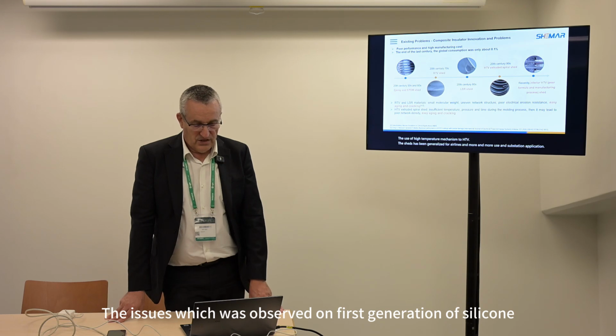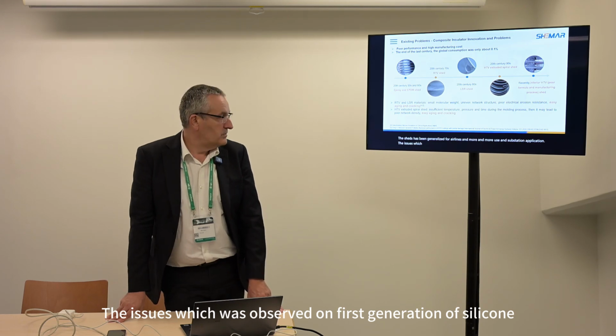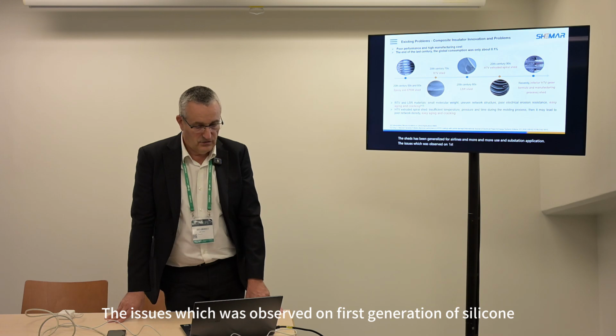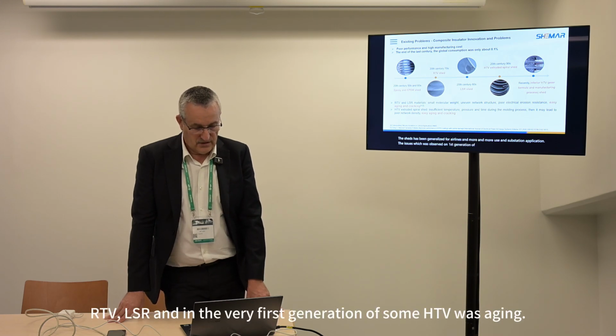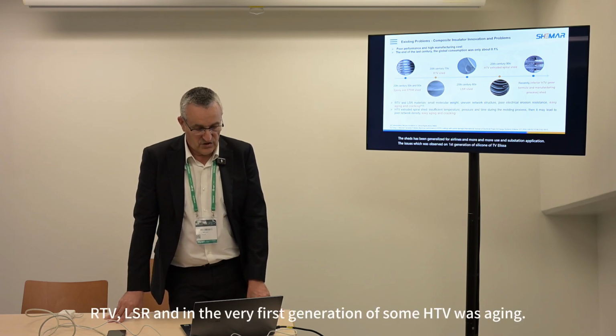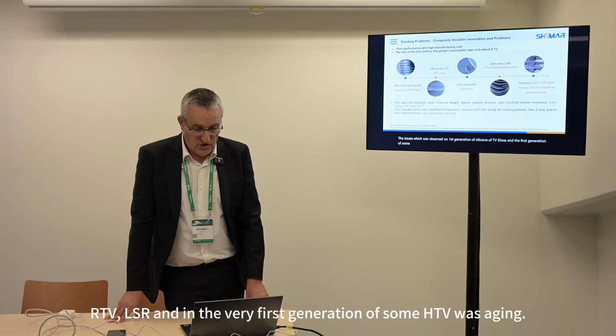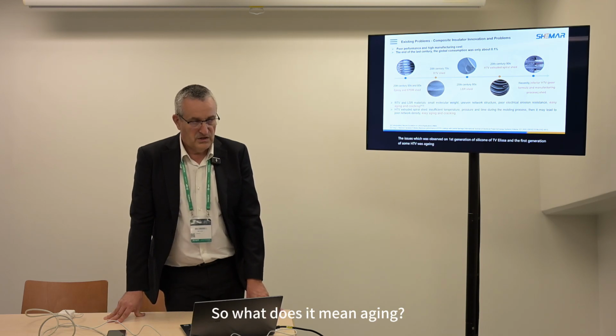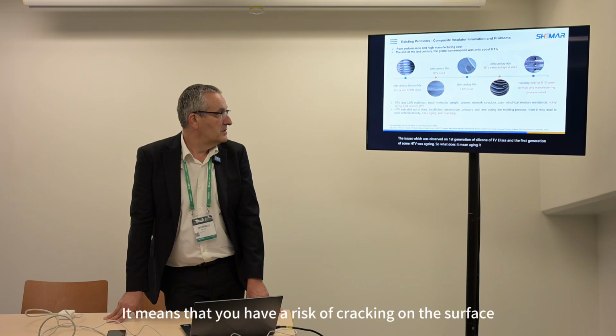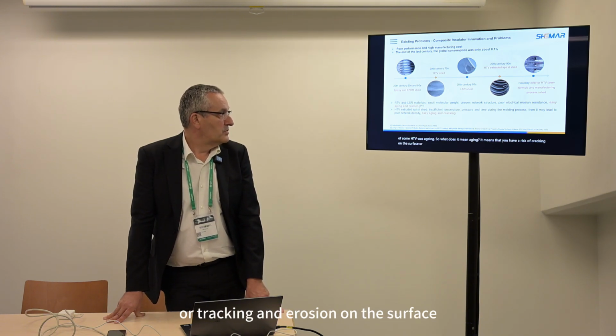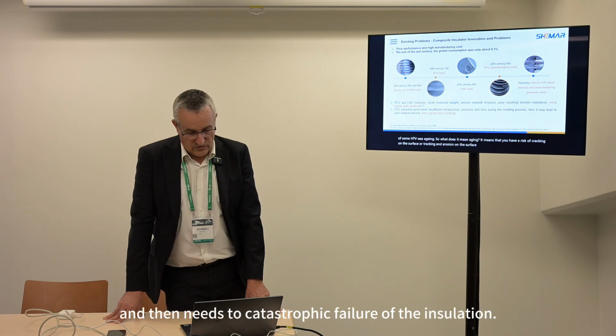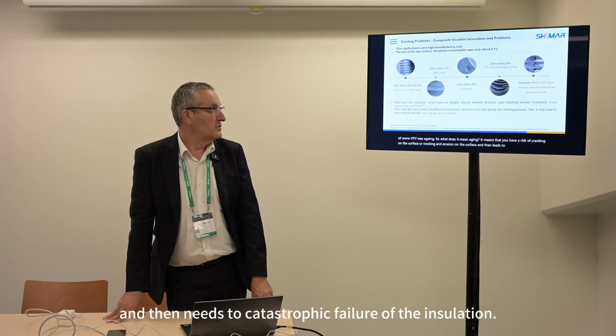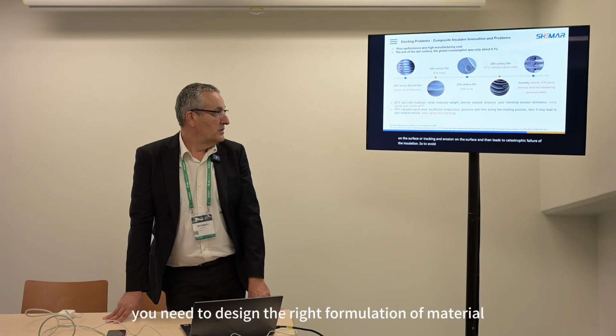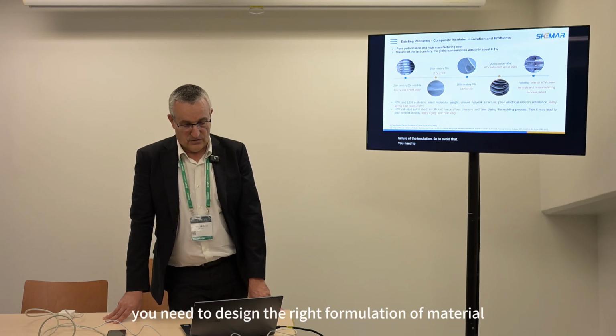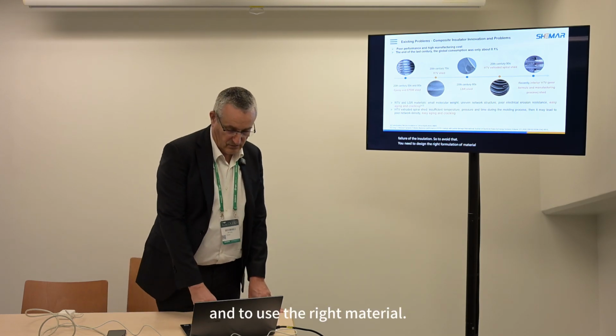The issue which was observed on the first generation of silicone, RTV, LSR, and the first generation of some HTV was aging. What does aging mean? It means that you have a risk of cracking and erosion on the surface, which then leads to catastrophic failure of the insulation. So to avoid that, you need to design the right formulation of material and use the right material.